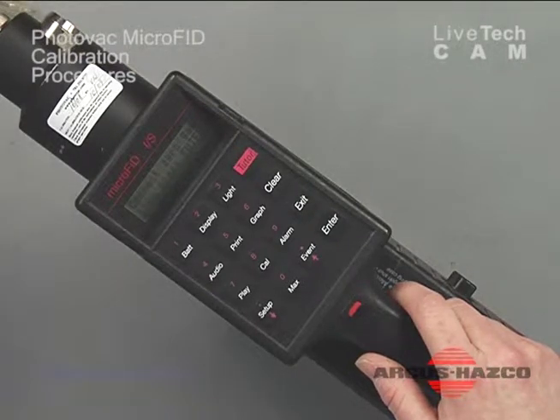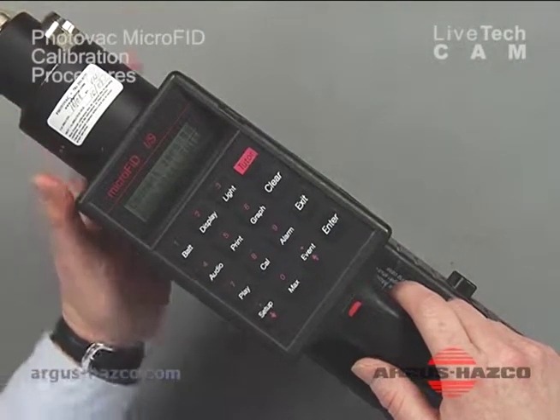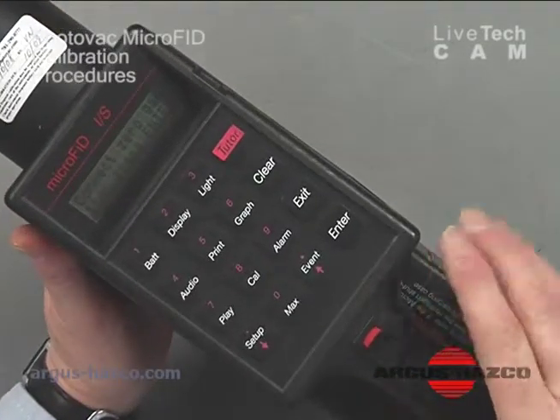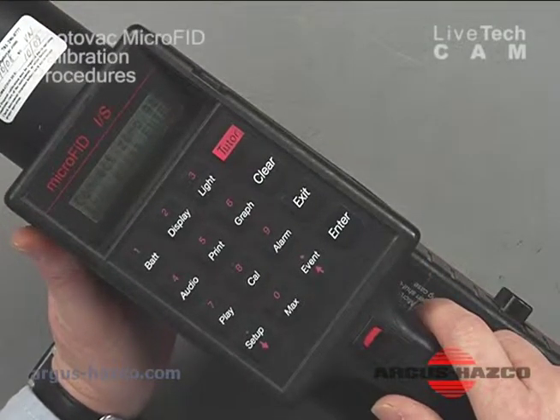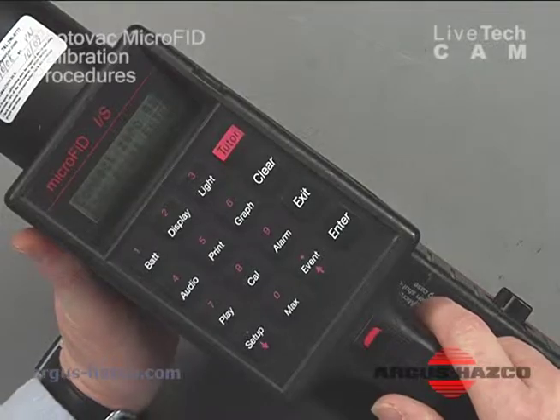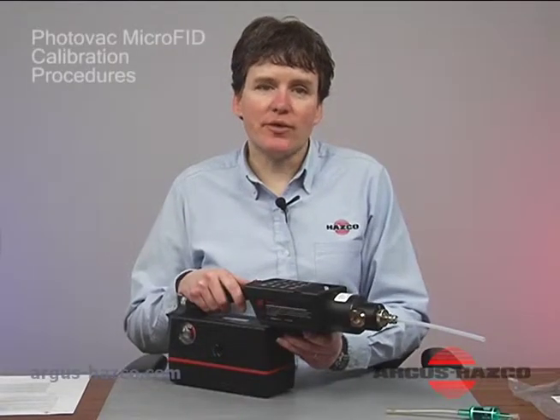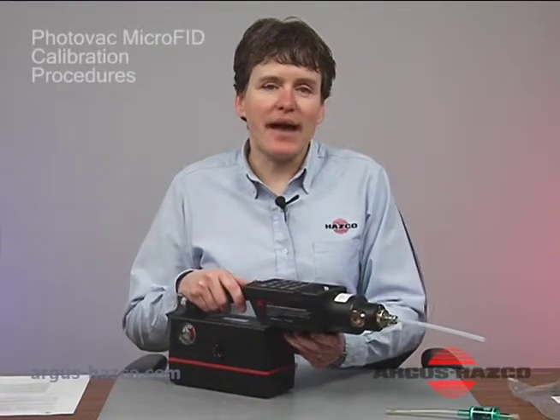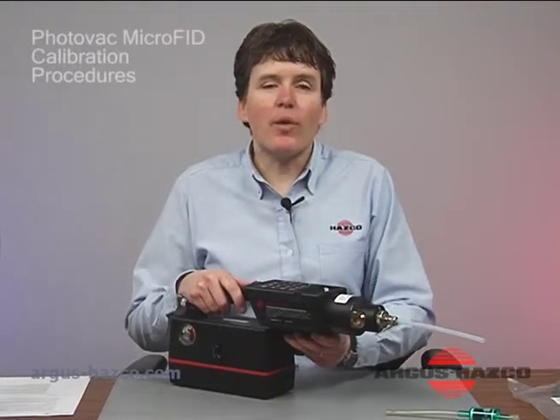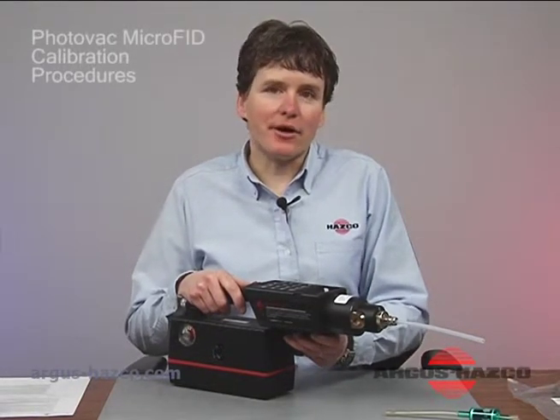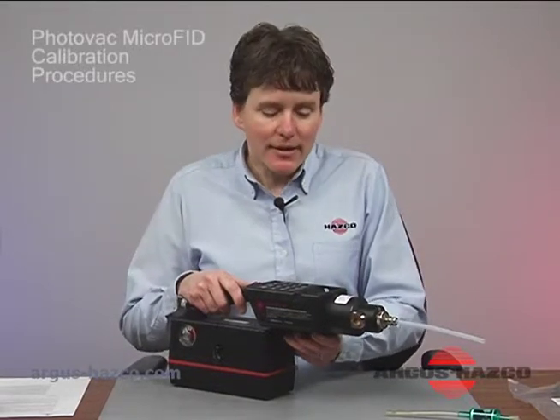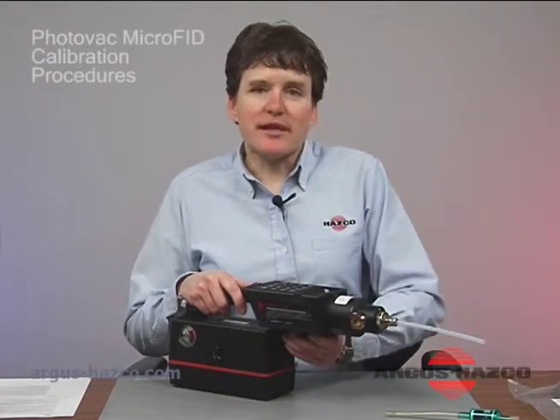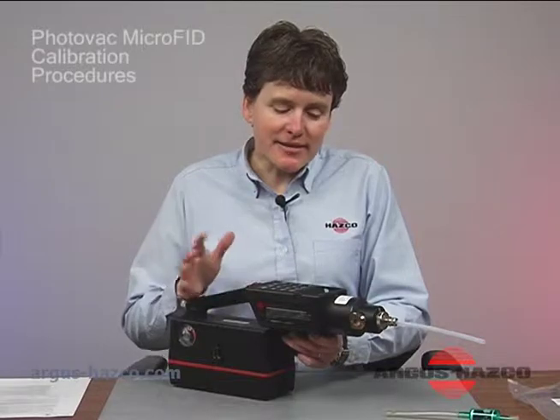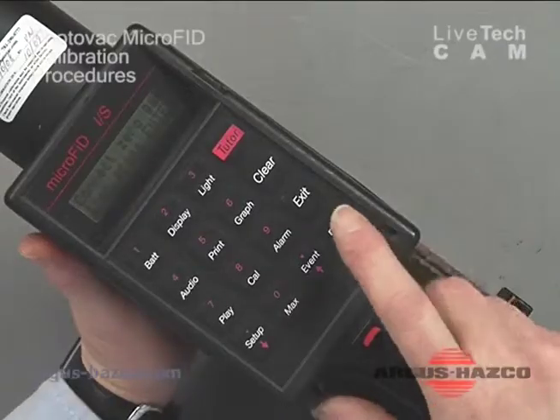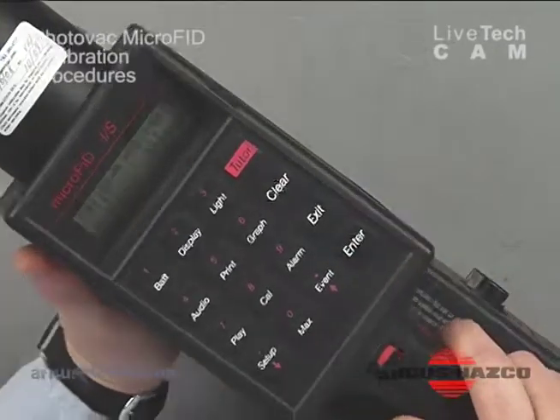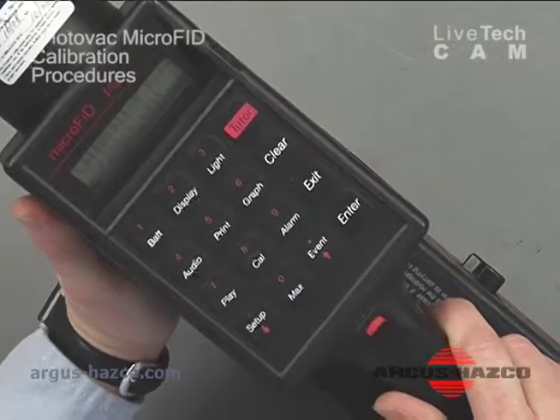So you do want to make sure that you are in a clean environment away from where you'll be detecting your methane with this unit. And also, if you are in a dirty environment, you can purchase zero grade air. Zero grade air is clean atmospheric air that has less than 0.1 ppm hydrocarbon in it. What we're going to do is just press my enter key because I'm in a nice clean environment. The unit will say calibrating now, please wait.